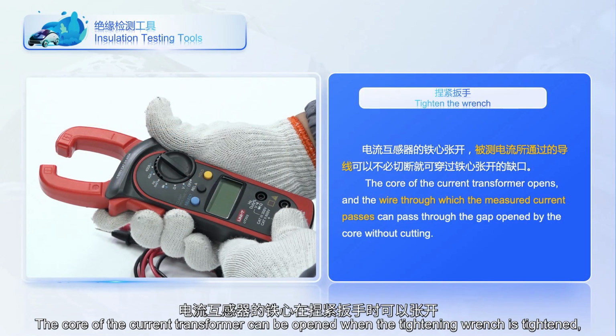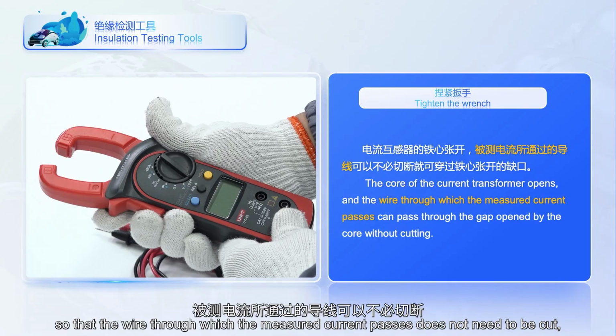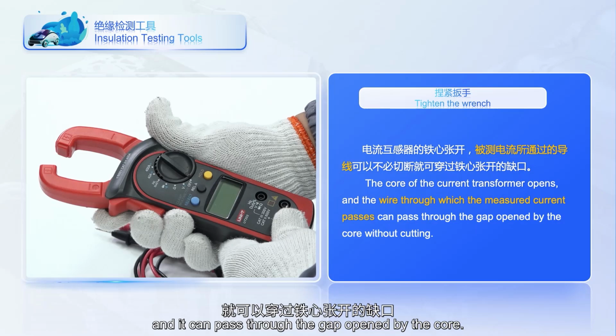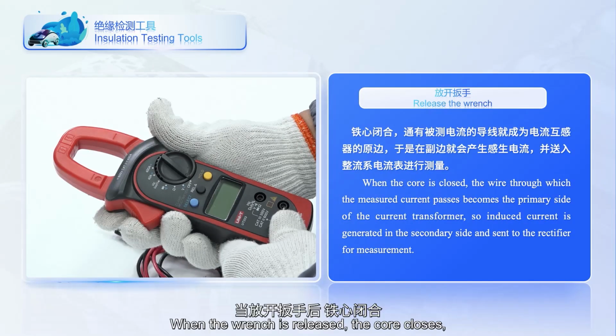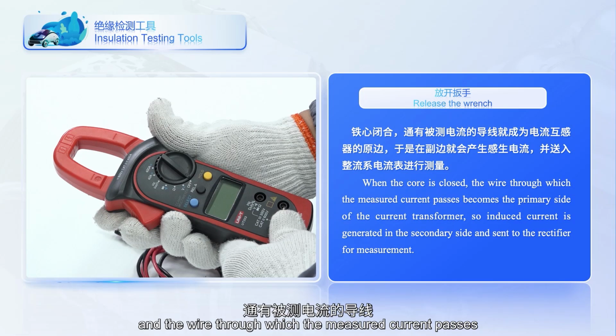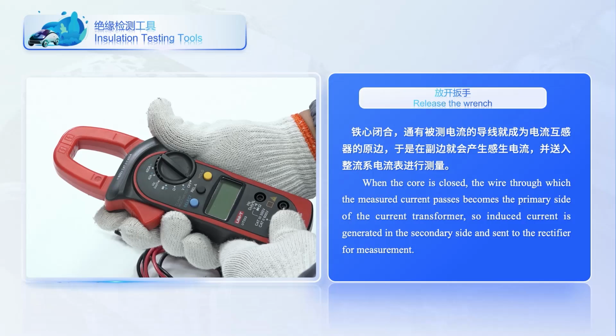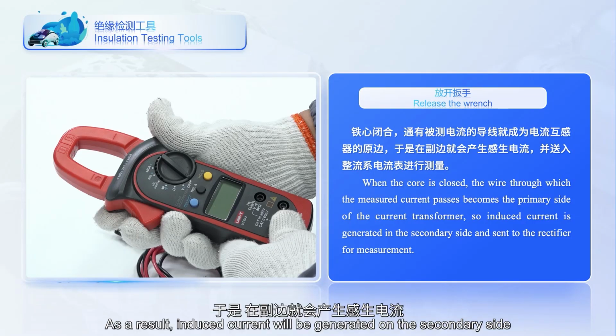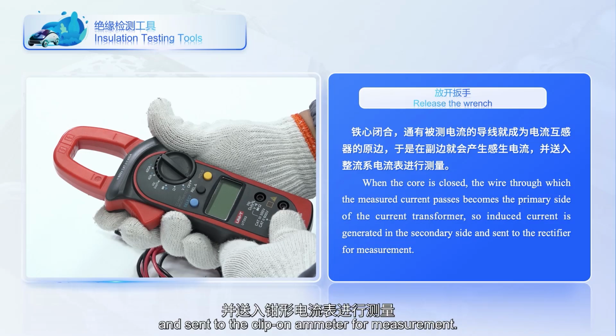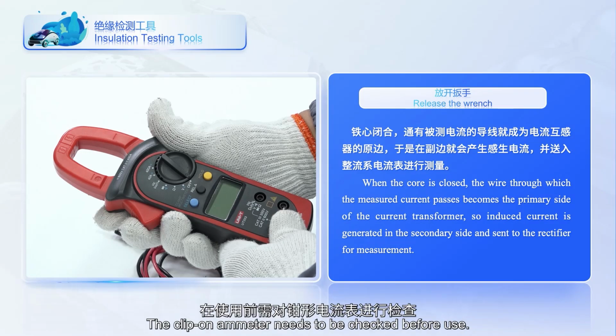The core of the current transformer can be opened when the tightening wrench is tightened, so that the wire through which the measured current passes does not need to be cut, and it can pass through the gap opened by the core. When the wrench is released, the core closes, and the wire through which the measured current passes becomes the primary side of the current transformer. As a result, induced current will be generated on the secondary side and sent to the clip-on ammeter for measurement. The clip-on ammeter needs to be checked before use.